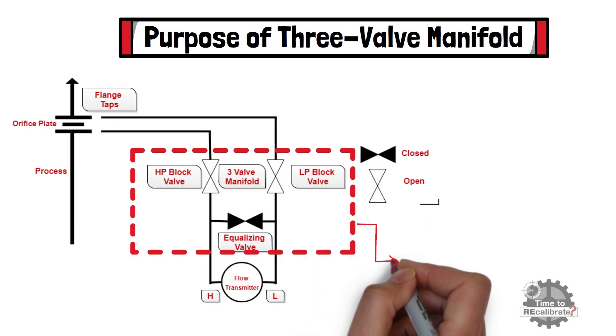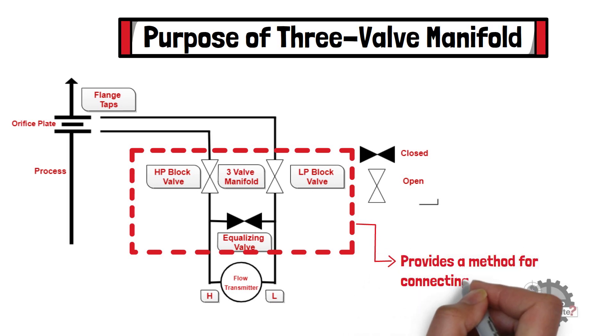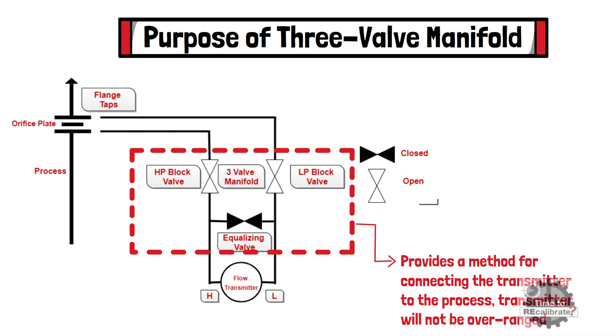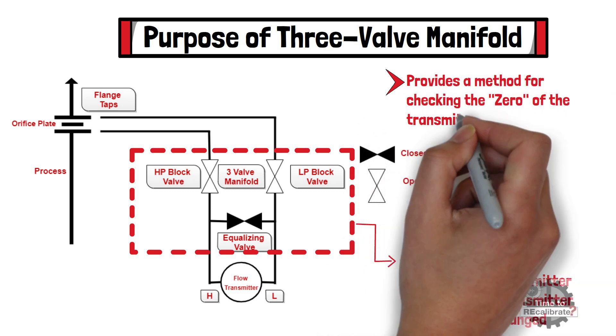The three valve manifold provides a method for connecting the transmitter to the process in such way that the transmitter will not be overranged while being removed or put into service. It also provides a method for checking the zero of the transmitter without removing it.